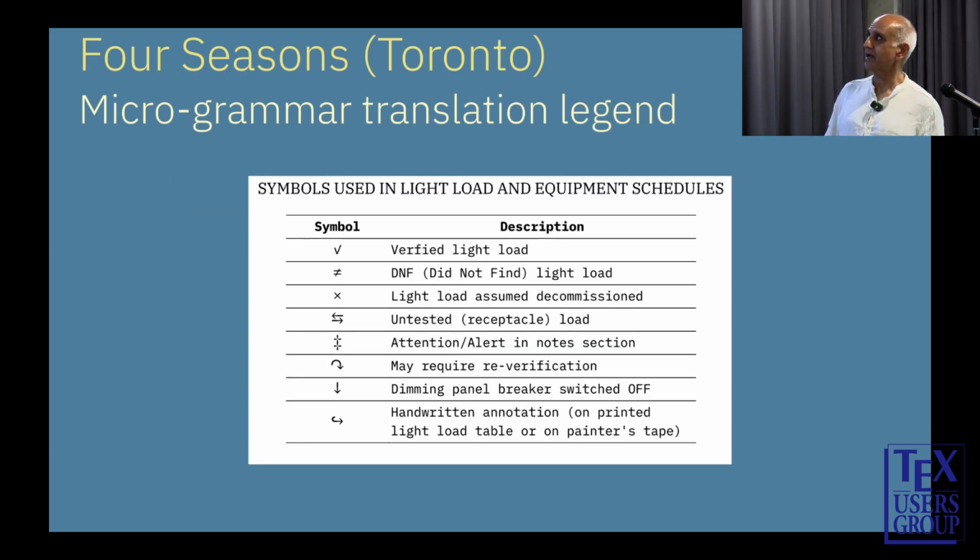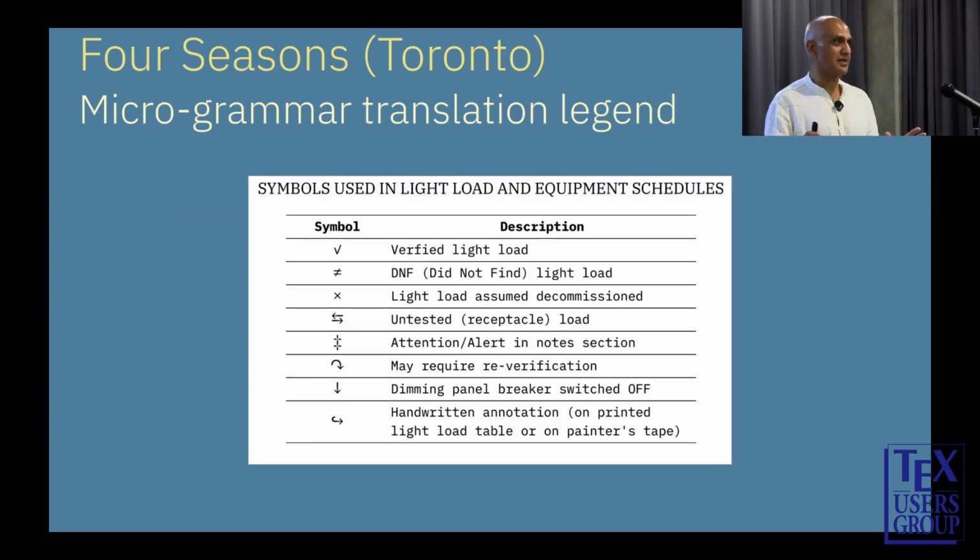And this is the legend. And before we begin, Barbara, Carl, I'm so sorry, there's a spelling mistake. Verified is misspelled. I can assure you this was an early version when the screenshot was taken. It did not hit the final report. But I want everyone to notice this part. We actually took note of this: handwritten notation on printed light load table or on painter's tape. Sometimes a technician will put some note on the breaker with painter's tape, just the way we have there.